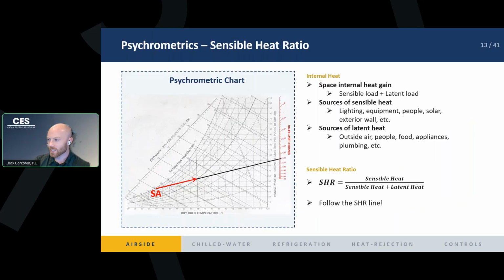And then lastly, sensible heat ratio is an important term that we need to know as engineers as well. If you have a room, what is sensible heat ratio? It's going to be the ratio of how much sensible heat to the total heat in your space, right? So your internal space, your occupied space, has several sources of sensible and then sources of latent heat. They're listed out here, right?